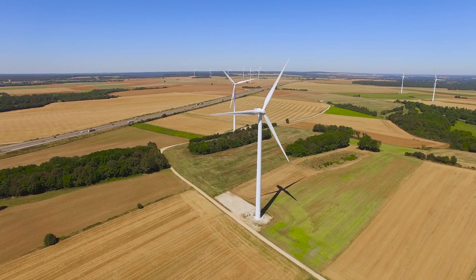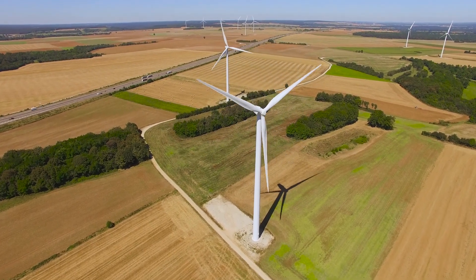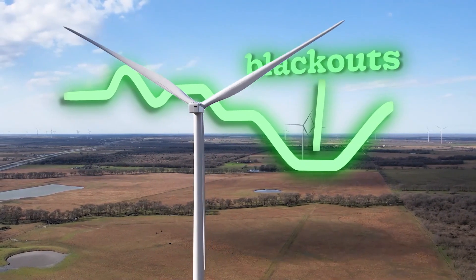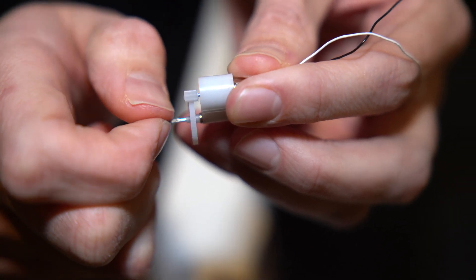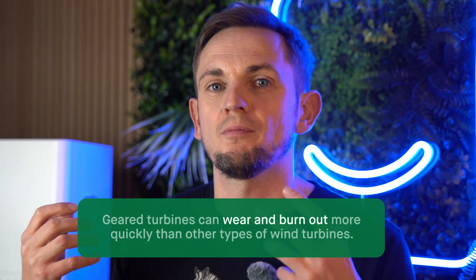Because you have different wind speeds — sometimes there isn't enough wind, sometimes there's too much — they have design features to try and regulate the amount and speed of the rotations. When the wind turbine is up to the correct speed, it's producing energy consistently. But when it drops away, the grid suddenly loses that inertia, and this is what is causing the issue. There are other types of turbine too — some have gearboxes, which allow us to get into that operational window much easier by gearing down the main turbine shaft. The issue with gearbox wind turbines is that they do burn out over time, creating lots of maintenance and additional cost.